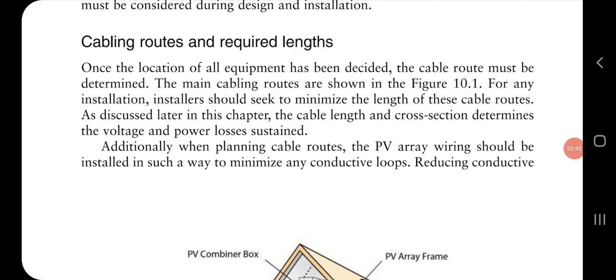Care has to be taken in designing the cables: cable routing and length required. Once the location has been decided, the cable routing is very important. The cable routing should be such that the minimum length of cable is used, because the shorter the cable length, the less the voltage drop and the losses.